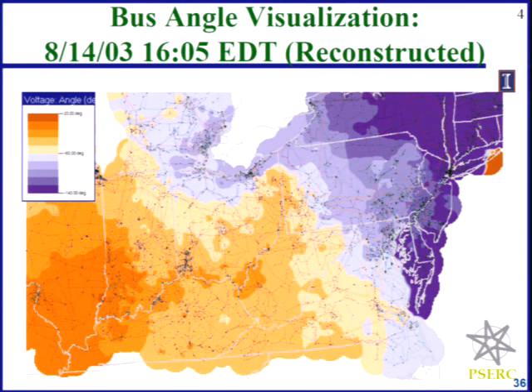Voltages go more on differences. VARs, which is the imaginary or reactive part of the power, flow more as a difference in voltages. That's why VARs don't travel very far in the system. That's why you need lots of local voltage control all over the system, because you want your voltage profile to be flat, to not allow VARs to travel. Probably doesn't make a lot of sense, but it does to us transmission guys.